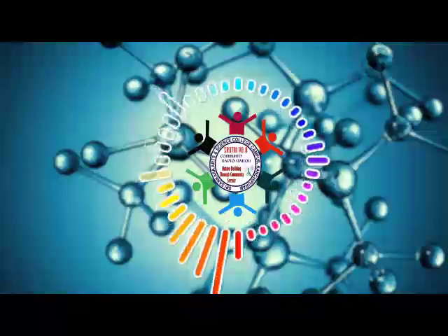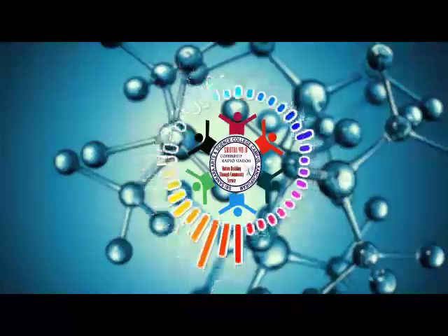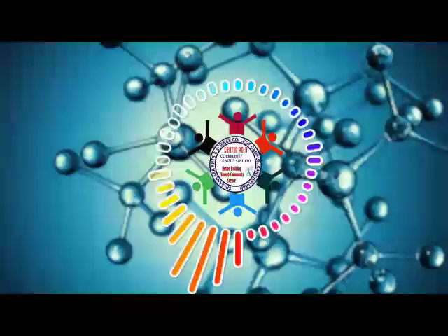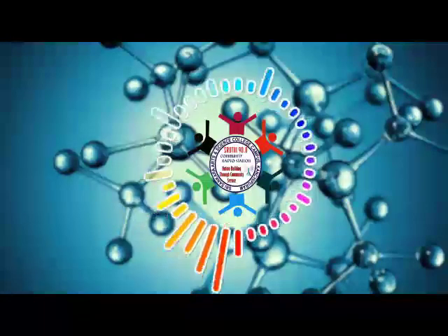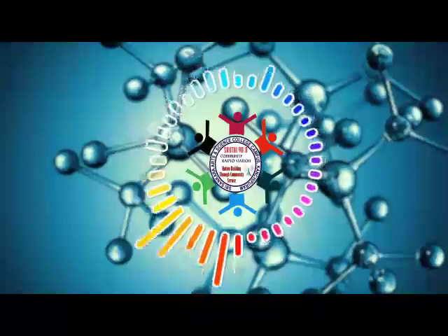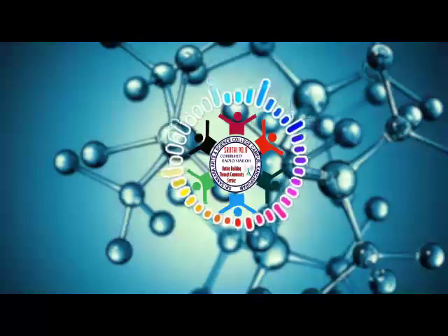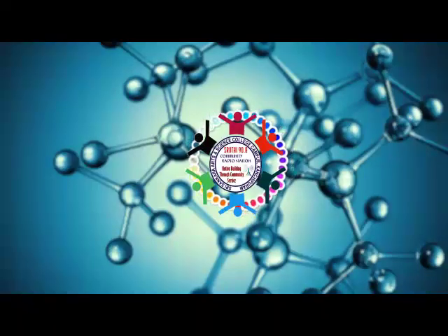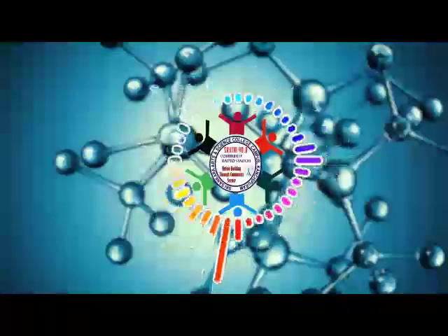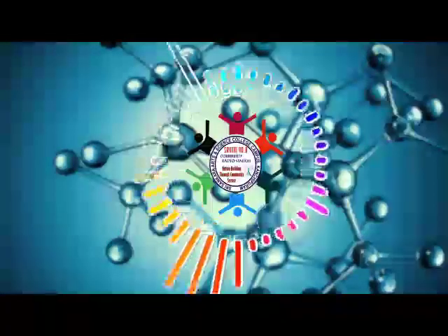Next one is mineral insulating oils. These oils are obtained from crude petroleum by distillation and have high oxidation resistance and good thermal stability. These are used in transformers and capacitors. Transformer oil is an important mineral insulating oil with high dielectric strength, viscosity and cooling property. This oil is used for insulating and cooling of transformers. It transfers heat by convection from the winding to the cooling surface. It maintains the insulation of windings.